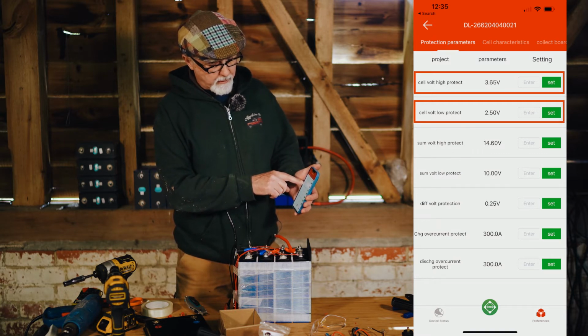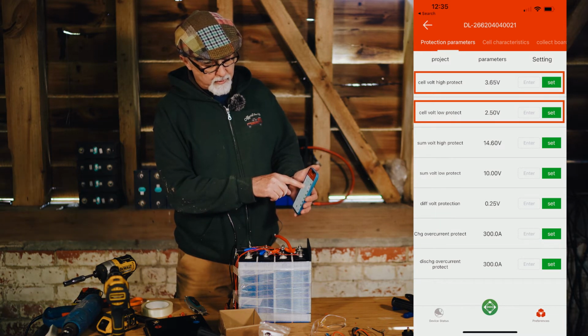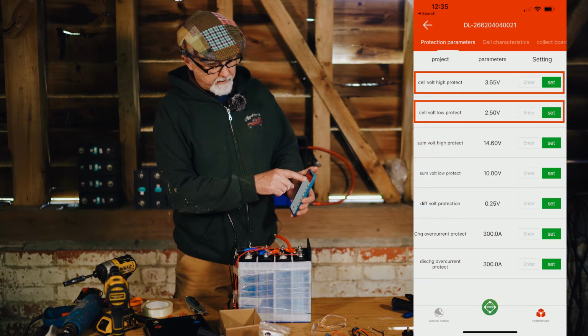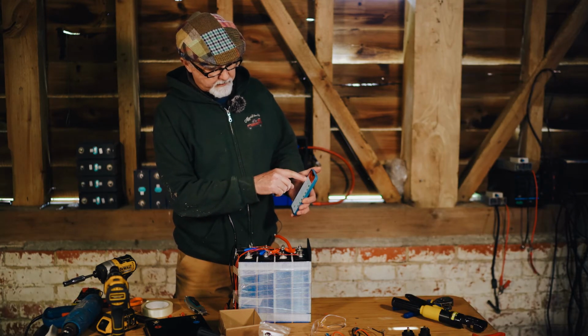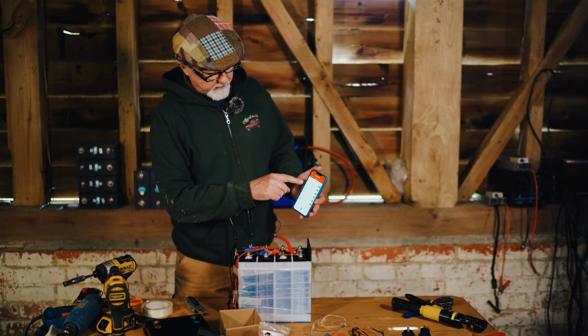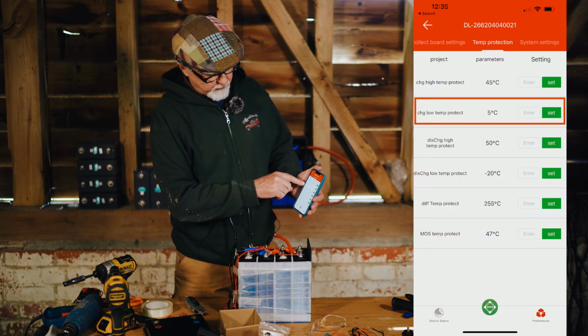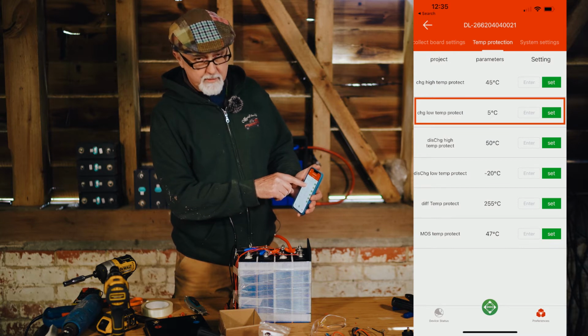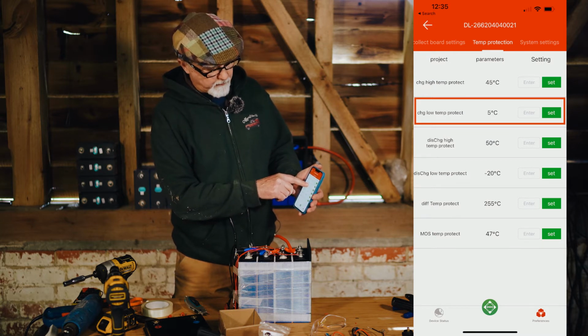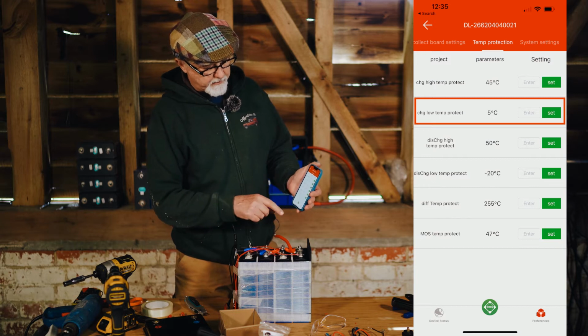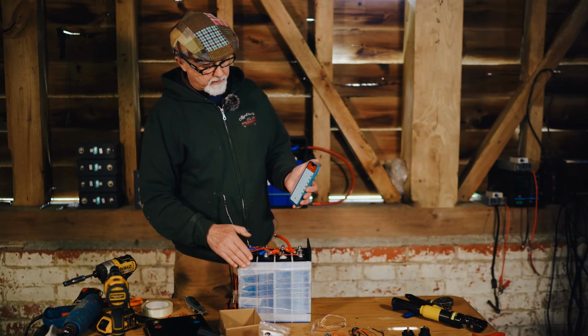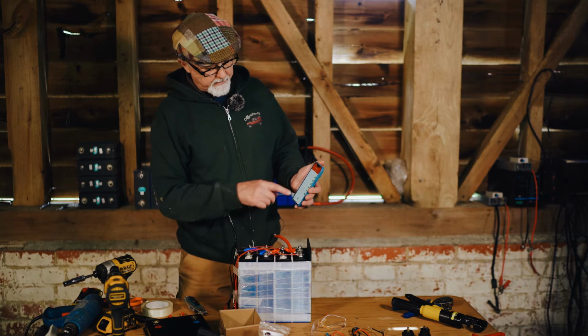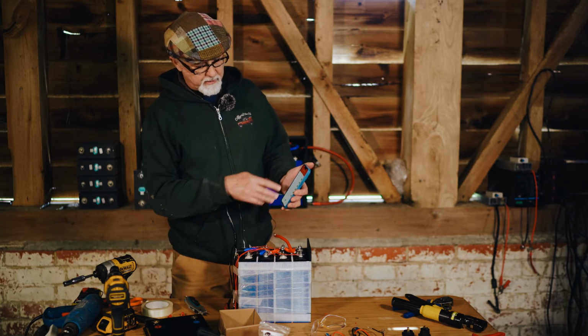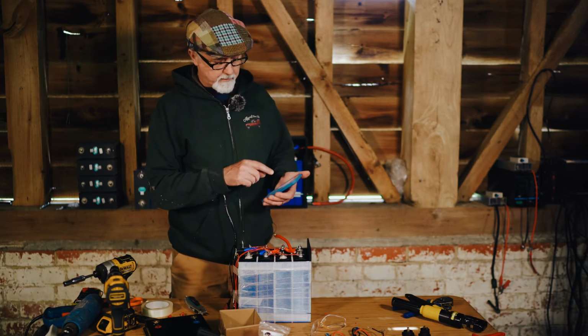Your cell volt low protect is set at 2.2 by default, change that to 2.5. Then you swing right across to temperature protection, and your charge low temperature protect will be set at -40, which is crazy for LiFePO4. So set that to 5 degrees centigrade, so it'll stop charging when it goes below 5 degrees centigrade. All of the other settings are quite fine, you can change them if you want, but the defaults are quite fine.